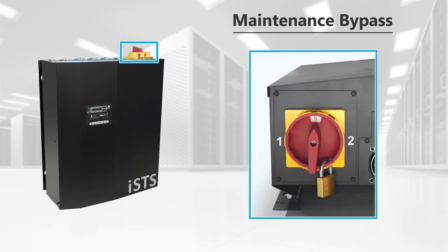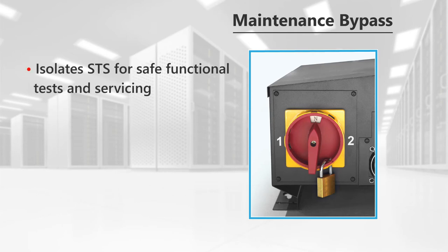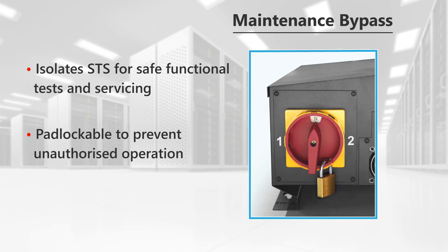The Model W features a maintenance bypass for no-break transfers to either Source 1 or Source 2. Maintenance bypass mode isolates the STS portion and makes the unit safe to perform functional tests and servicing. The switch can be padlocked in any position to prevent unauthorized operation.